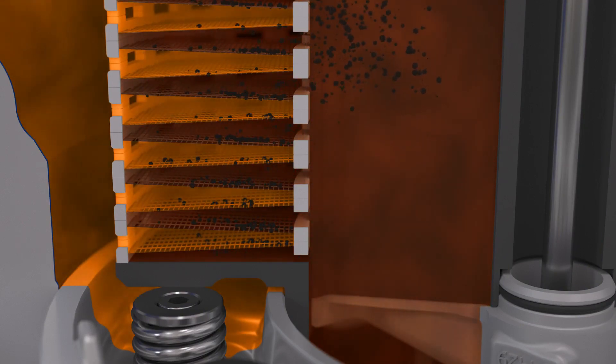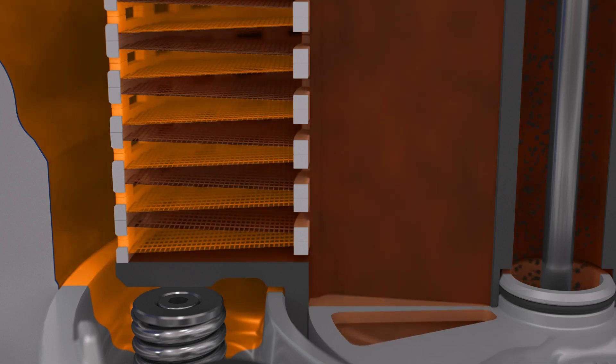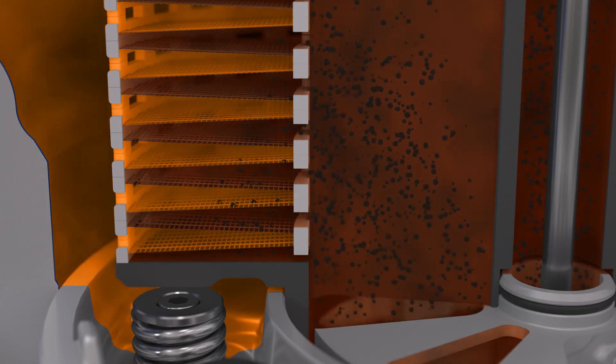The filtration capacity is always maintained thanks to continuous back flushing, which ensures no solids are retained on the surface of the filter mesh. This is done at the same time as the oil is being filtered and pumped to the engine, leading to a constant and very low pressure drop across the filter.